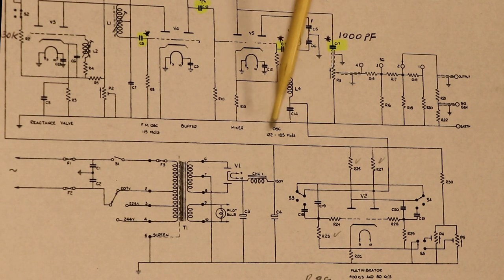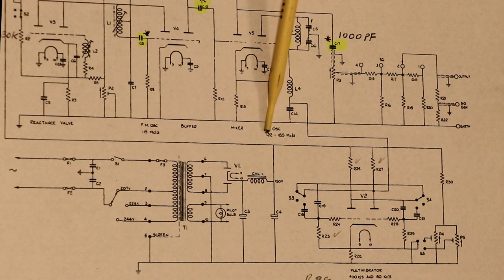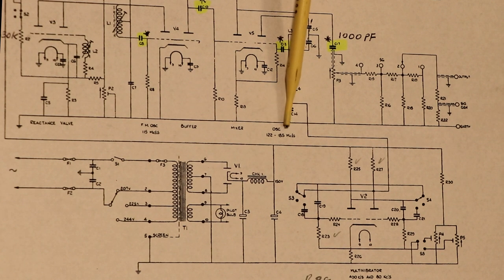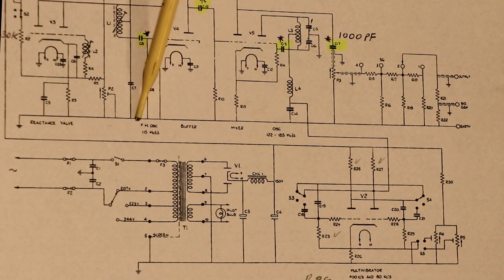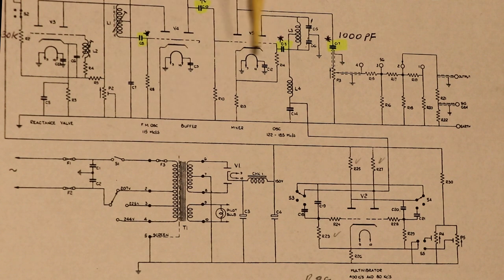This oscillator produces an output between 122 and 185 megahertz, but the actual output from the signal generator is only 7 to 70 megahertz. The way this works is it mixes this 122 to 185 oscillator with a 115 megacycles oscillator, and the output from the signal generator is a heterodyne.